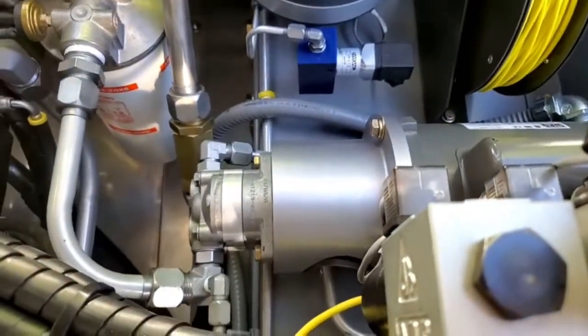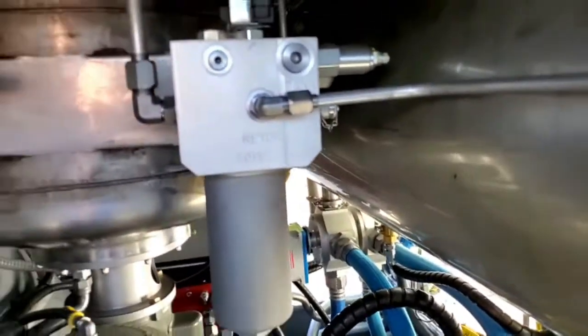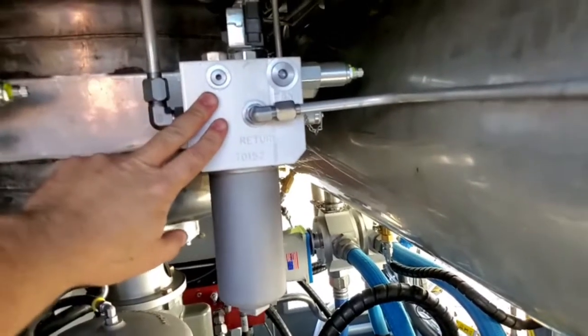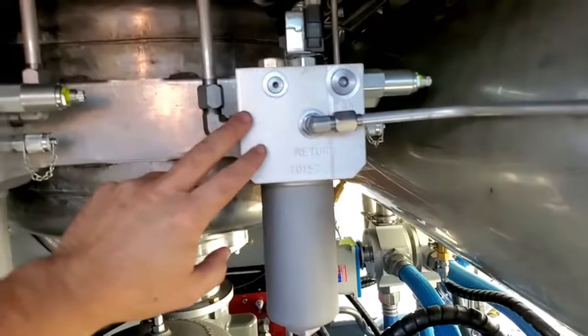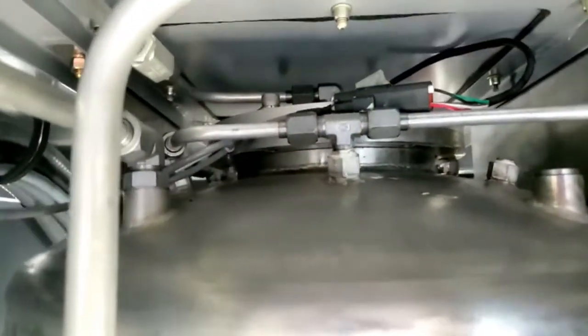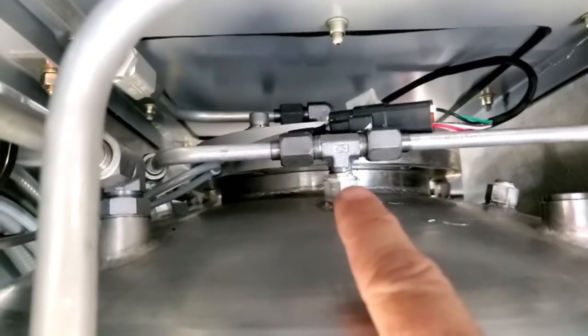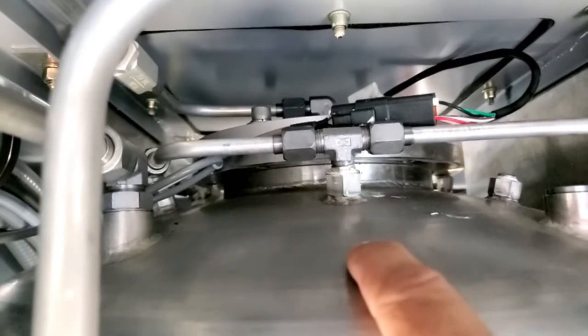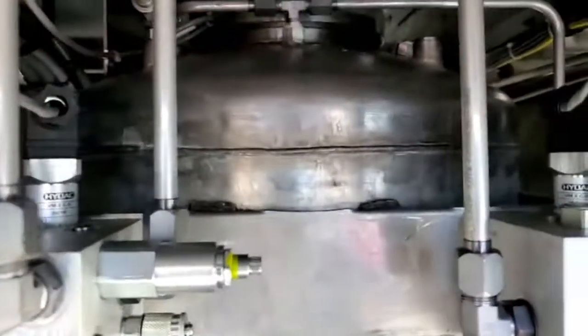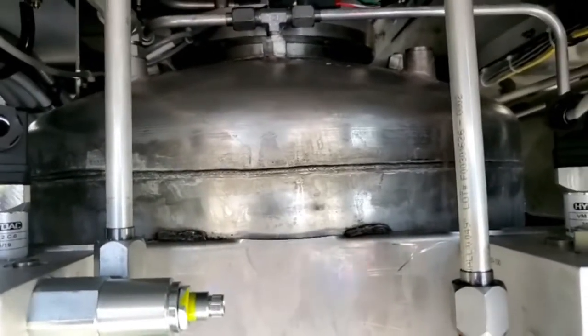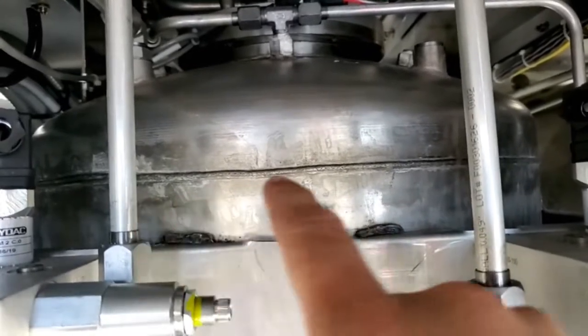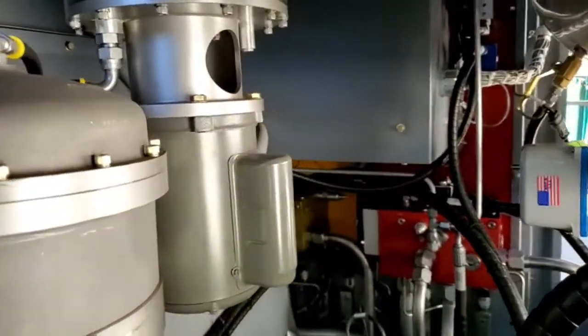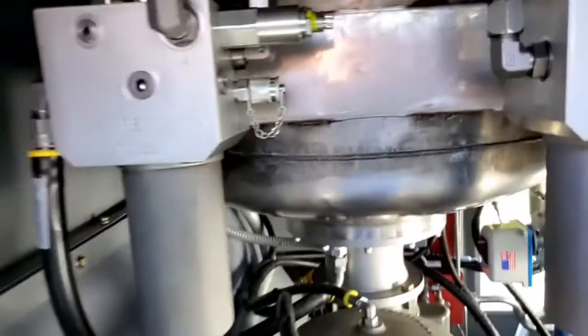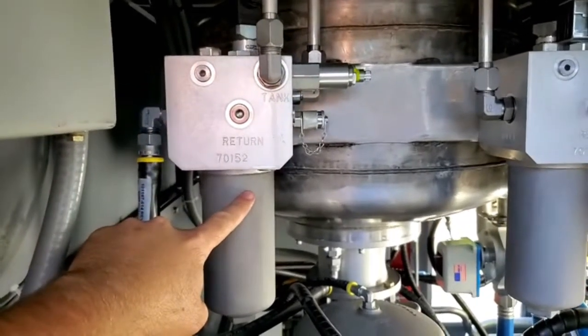After the moisture separator filter, it goes to the charge pump. The charge pump then pushes that fluid up the lines to the charge filter. From the charge filter, just 3 micron, it runs up into the top of the purification tank into nozzles. There's 5 of these nozzles all the way around the tank. The nozzles atomize the fluid inside the tank, turns it into a mist, and then that mist meets a welded in screen which turns it back into droplets. Those droplets fall to the bottom of the tank where the discharge pump draws that fluid out and sends it through the discharge return filter, which is also a 3 micron filter.